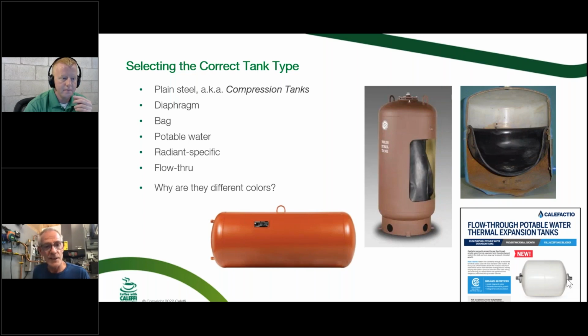And then radiant specific, I think I said earlier, Amtrol made a tank called a Radiant-R tank that was a lined tank. So if you're on there non-barrier, I believe that's getting replaced by a newer version. Cody, did you talk? Yeah, I think it was the Extrol Pro is what they call it, and it was a stainless nipple with a lined tank and everything like that, so it could handle any oxygen ingress if you have a radiant system that is using non-barrier tubing, where you could have excessive amounts of oxygen in there. And I think it comes with that little indicator cap too as part of that new version.